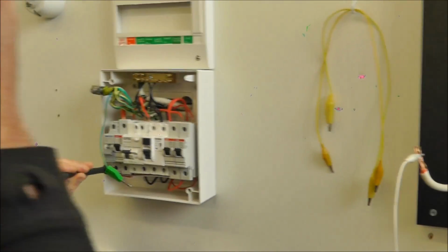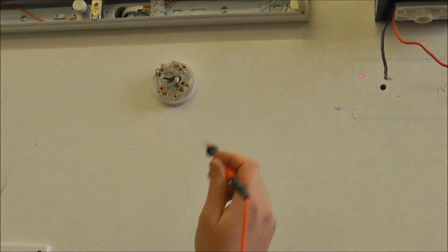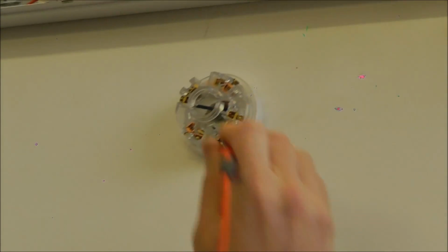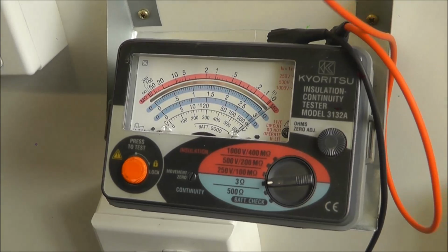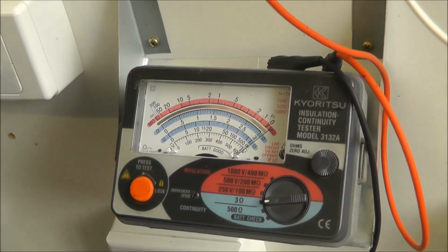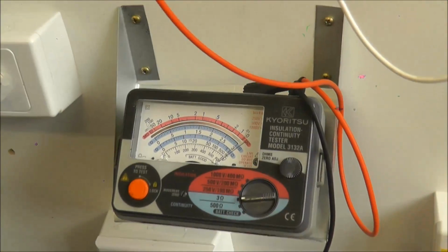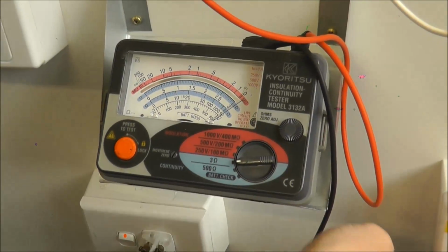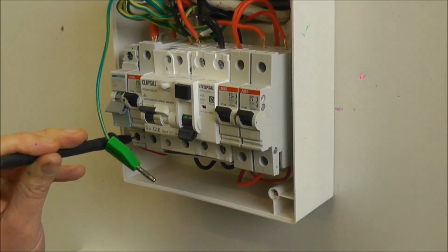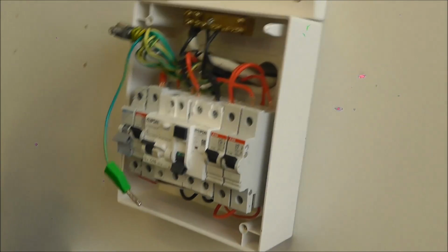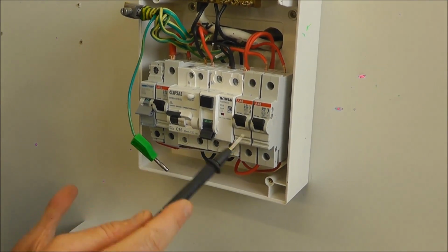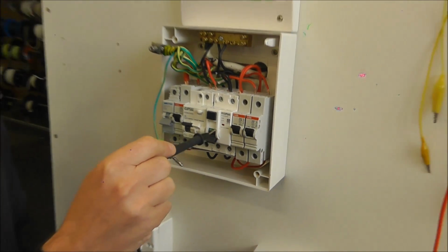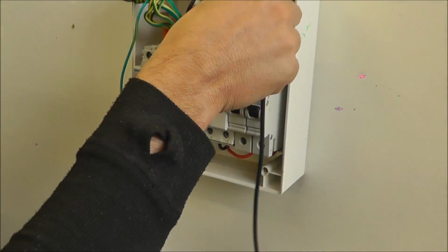Okay, lighting circuits over here. I'll go to the ceiling rose, bottom right. I need an extra set of hands here. I'll just put that up there. Oh, that's in there. Ceiling rose. Oh, it's tripped then. Okay, now, is that a bad thing? I don't really think that's a bad thing. It's just taken the RCD out. So now I know that it must be somewhere over here. I'll leave the RCD off and I'll follow my nose around here.